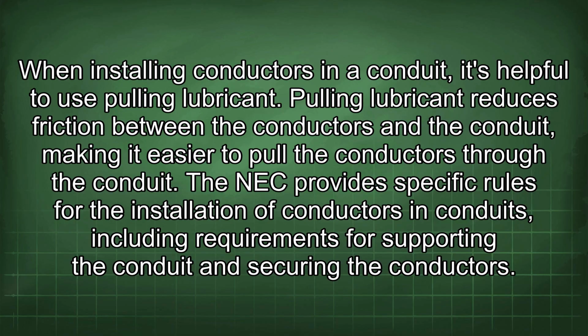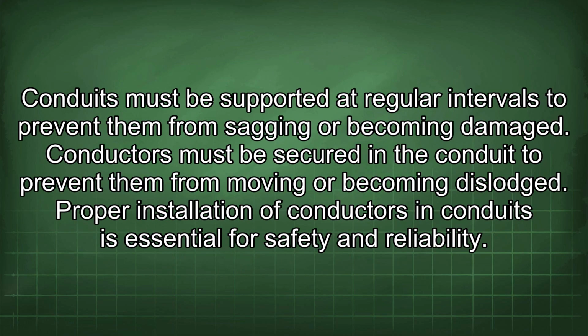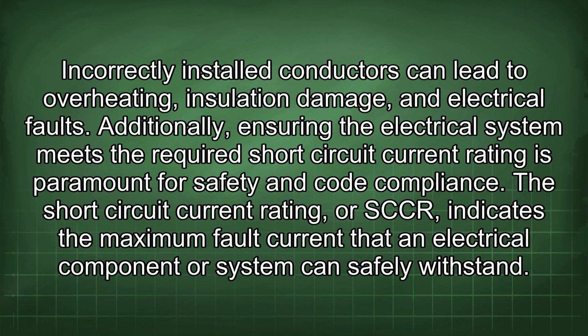The NEC provides specific rules for the installation of conductors in conduits, including requirements for supporting the conduit and securing the conductors. Conduits must be supported at regular intervals to prevent them from sagging or becoming damaged. Conductors must be secured in the conduit to prevent them from moving or becoming dislodged. Proper installation of conductors in conduits is essential for safety and reliability. Incorrectly installed conductors can lead to overheating, insulation damage, and electrical faults.